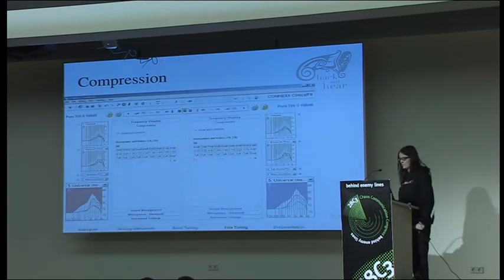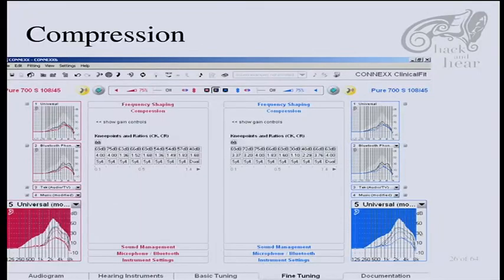In the hearing adjusting software, it looks like this. This is just an example from Siemens. Every brand has their own adjusting or tuning software. Here you have the knee point in the first row and the factor by which it is compressed. The third row is a factor for how fast it should react. Syl means syllable, so within one syllable it's adjusted to the right volume.